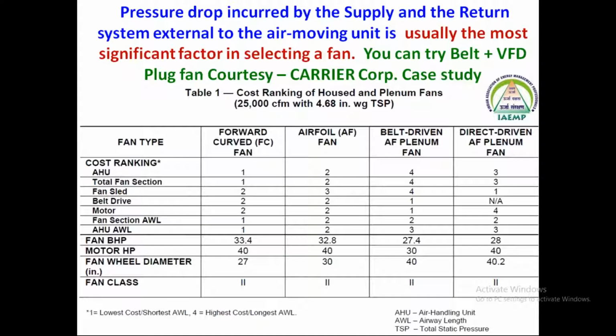Thanks to Carrier air conditioning for this case study. This is a fan delivering 25,000 CFM at almost 5 inches of water column, almost 125 mm of water column, 1250 pascals. That is the deliverable pressure from the fan. If you see the forward curved fan, it consumes almost 33 brake horsepower, that is the input power to the fan. You can see it in the fifth column, fan BHP. If it is an airfoil fan, it is 32. If it is a belt driven plenum fan or plug fan, it is only 27.